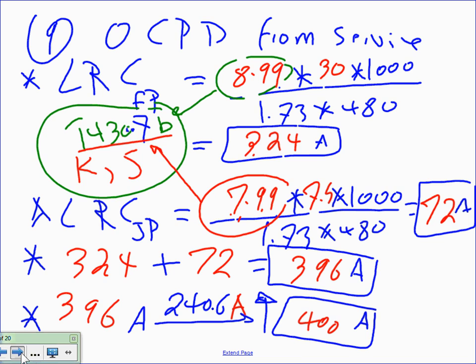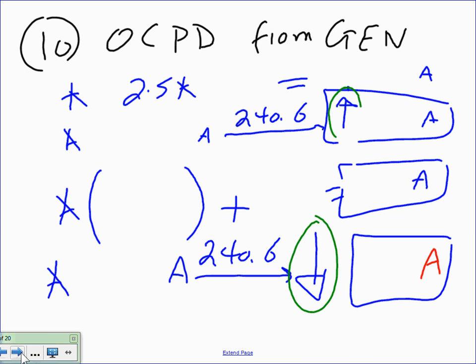Okay, so let's go, guys, to number 10. Number 10 is the overcurrent protection device that's coming out of our emergency generator. And you guys are lucky that I didn't ask you to size the emergency generator. By the way, Tao, if I asked you to size the emergency generator here, does everybody know how to size the emergency generator? We just sized one for us at Dunwoody. They're going to buy one to pick up a couple of sump pumps. Everybody knows how to size the generator. Remember the common software that we have?